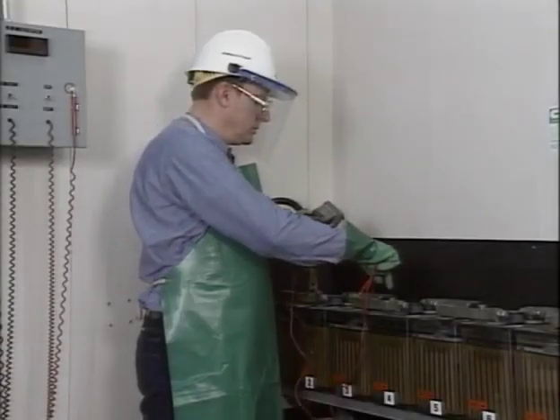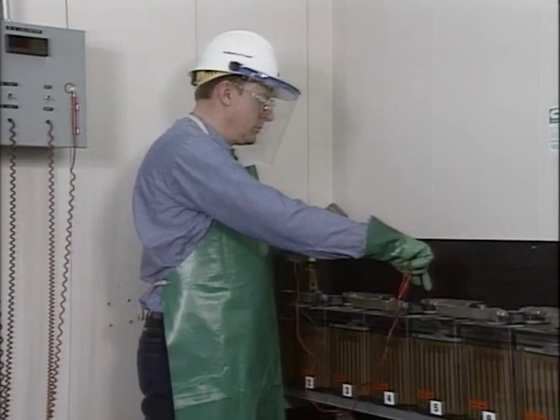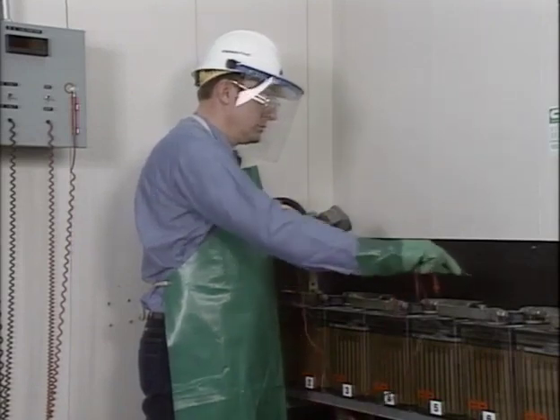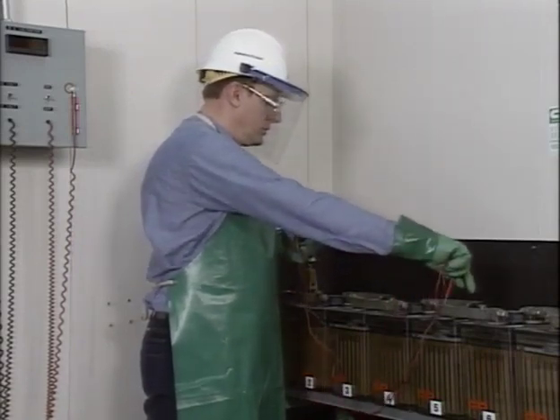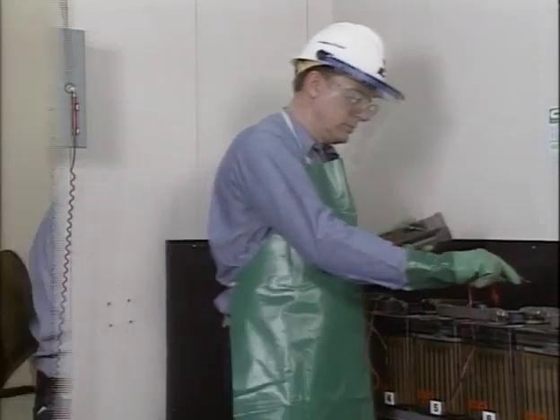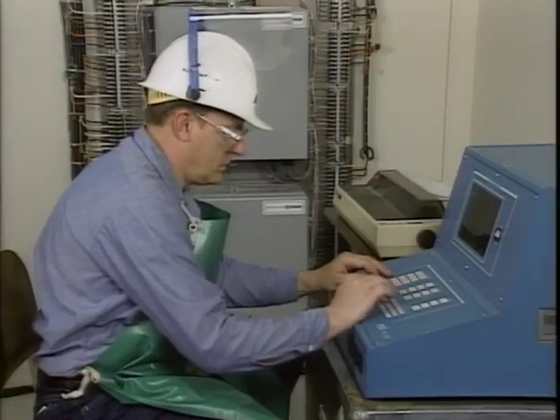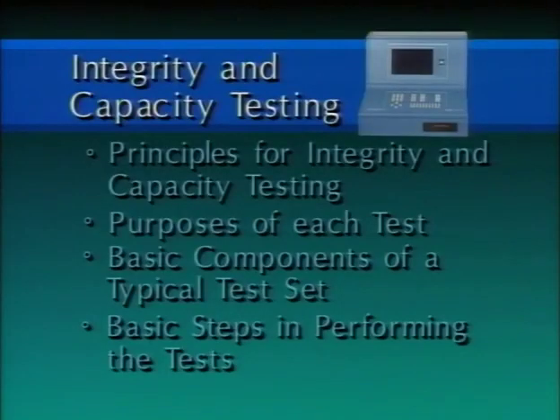Cell voltage and specific gravity tests provide a good indication of the state of charge of a battery, but they don't indicate if the battery is able to deliver the necessary power when needed. Two tests that do are the integrity and capacity tests. This part of the program will look at integrity and capacity testing of substation batteries. The key points that will be covered include the principles of integrity and capacity testing, the purpose of each test, the basic components of a typical test set, and the basic steps for performing the tests.